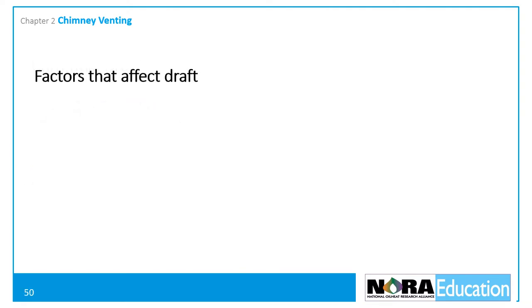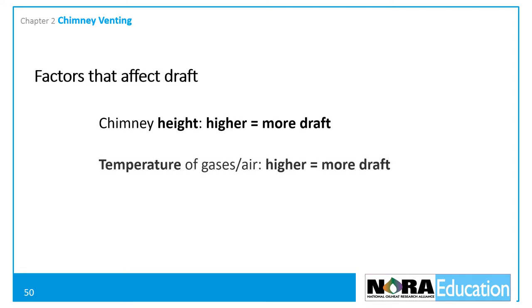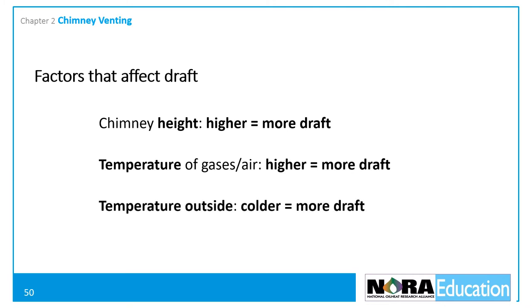Three main factors control the amount of chimney draft that is generated: the chimney height — the higher the chimney, the greater the draft; the temperature of the combustion gases — the hotter they are, the greater the draft; and the temperature of the air outside the building — the colder it is outside, the greater the draft.